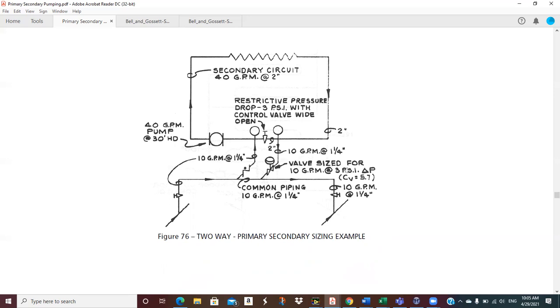Okay. And notice that the restrictive loss by this balance valve is set for the same 3 psi. So think about it, when the valve goes wide open, then I've got the same pressure drop here as I do here. So there's 3 psi with the valve wide open. So I'm splitting that drop. And then of course I've got other pressure drop in this system. And I'm not sure, I don't think that they have to be the same. I don't think they're saying that. It just in this example turned out to be. But this has to be set so that when this valve is open, we get the appropriate flow up through here.